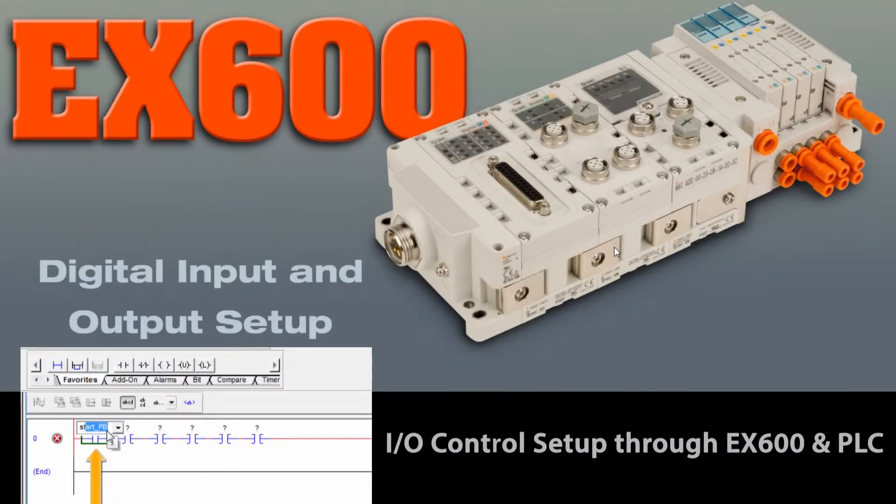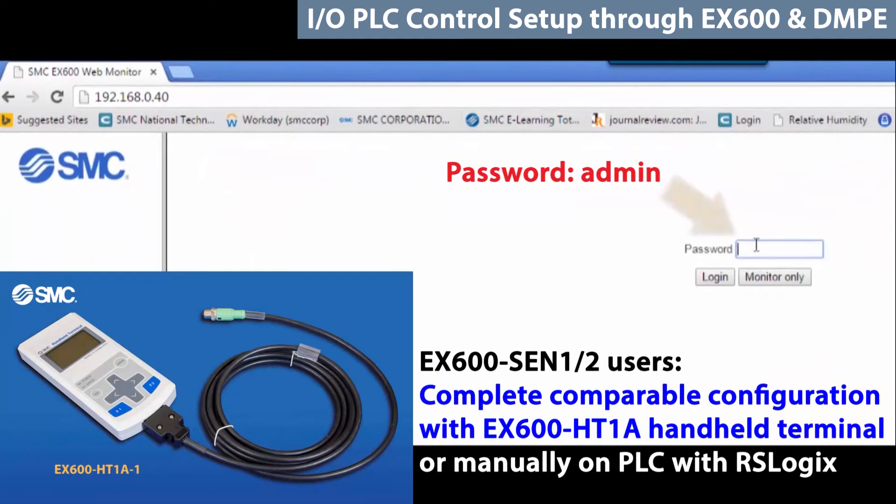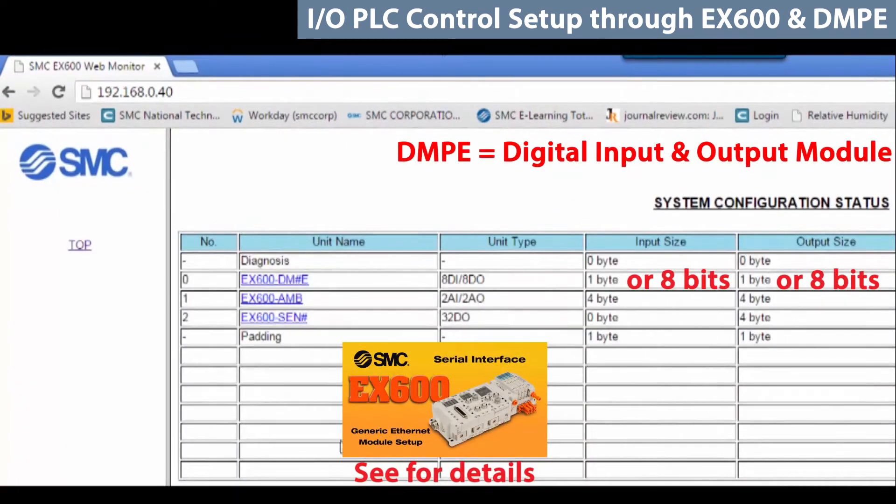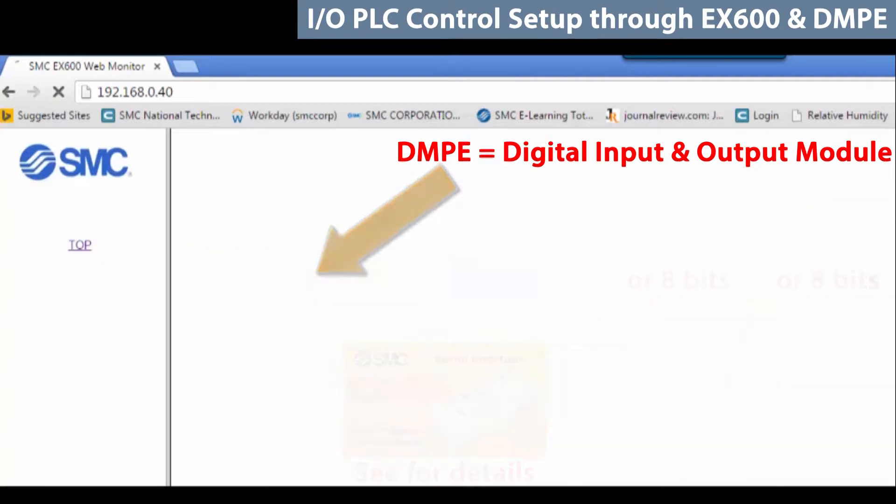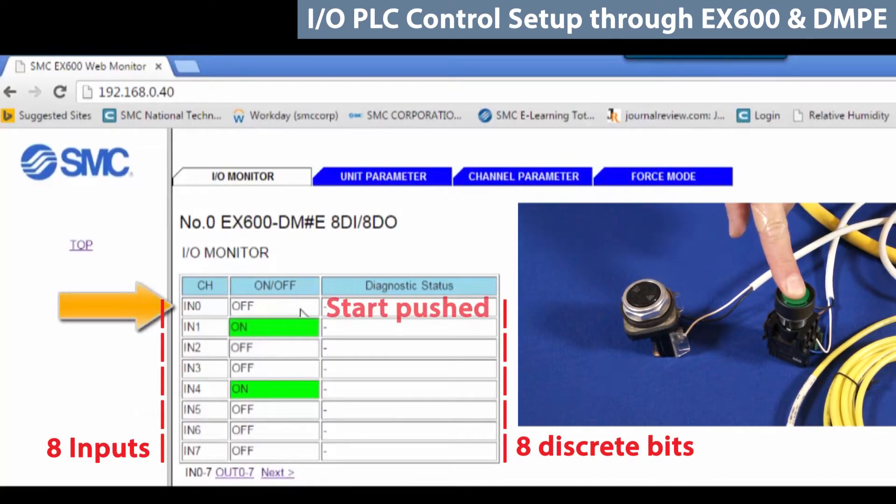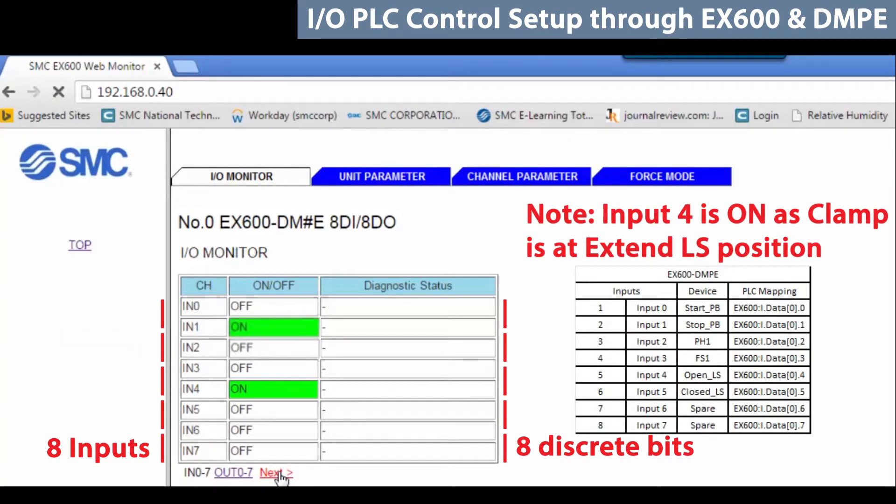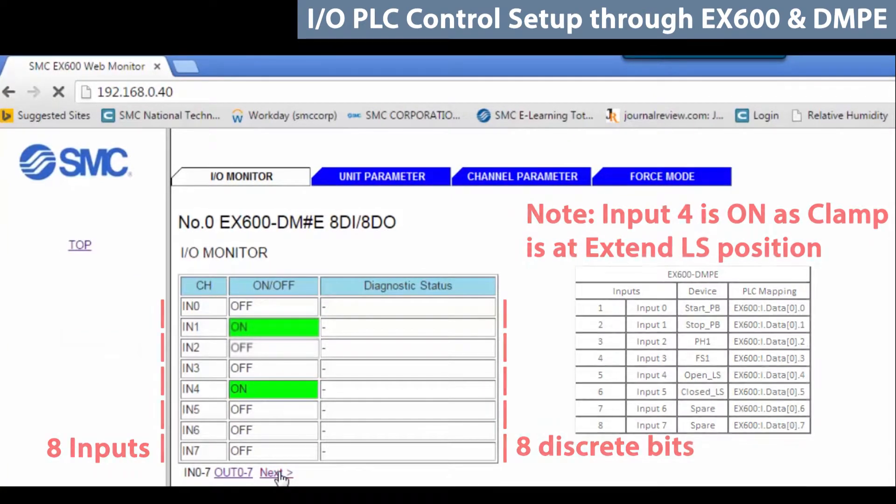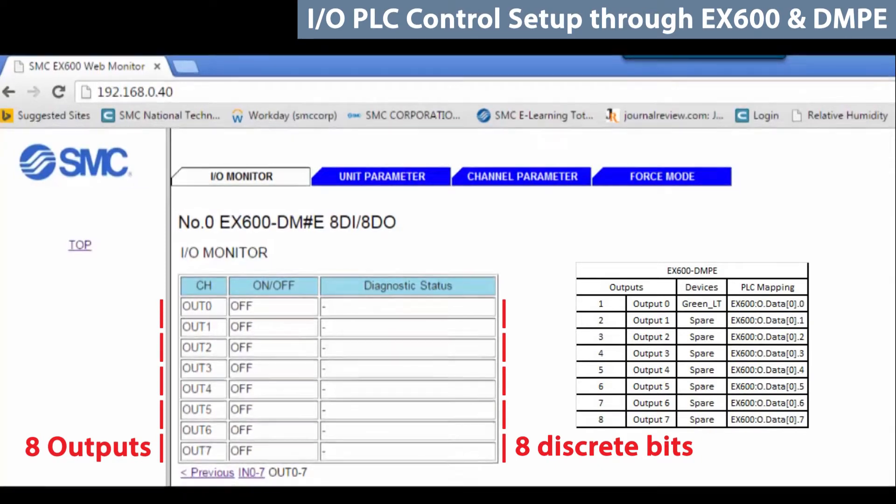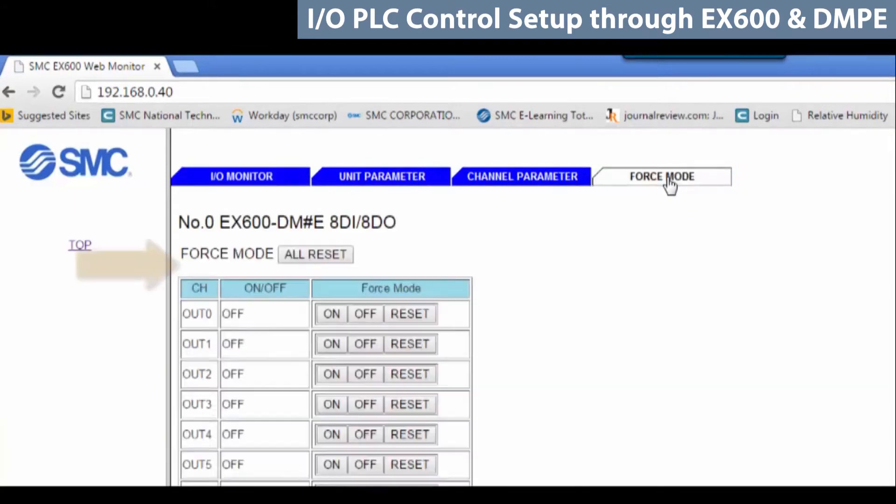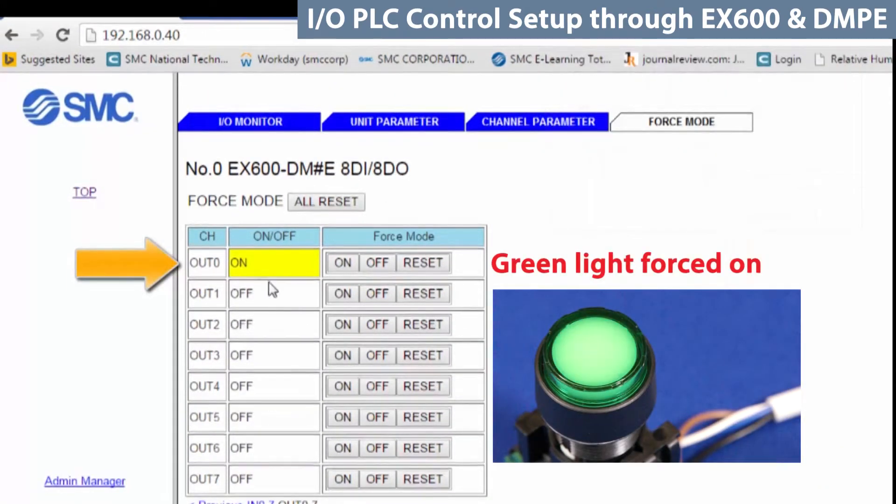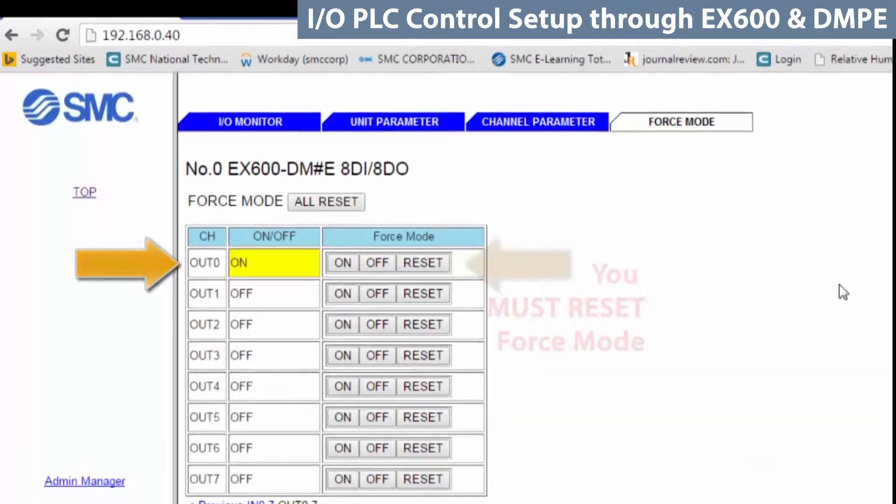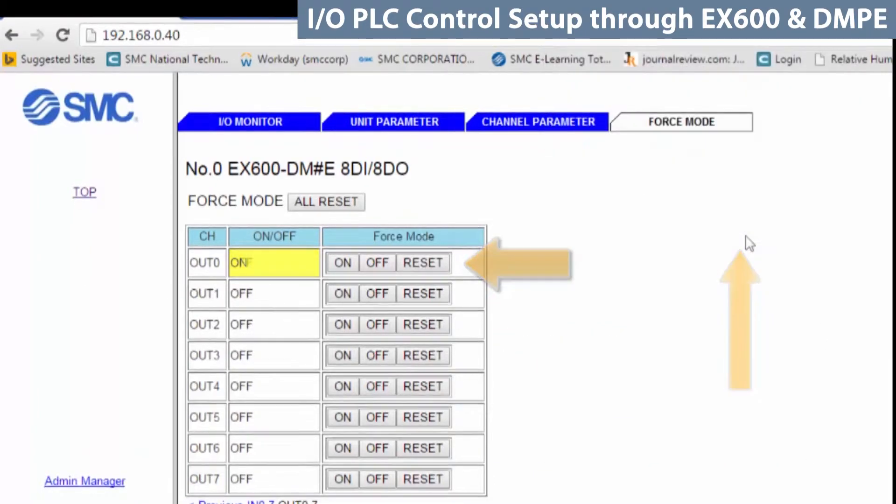Now, let's monitor the discrete I/O. Open up the EX600 web monitor and enter as an admin. Click on the DMPE module for digital I/O. Pushing the start button shows up as green on input 0. To see the outputs, click on OUT 0-7. Notice none of them are on because we've not started the PLC. To test the light output, go to force mode. Turn output 0 on. Notice the background is yellow now. The light should be on. Before leaving this screen, remove the force by clicking reset.